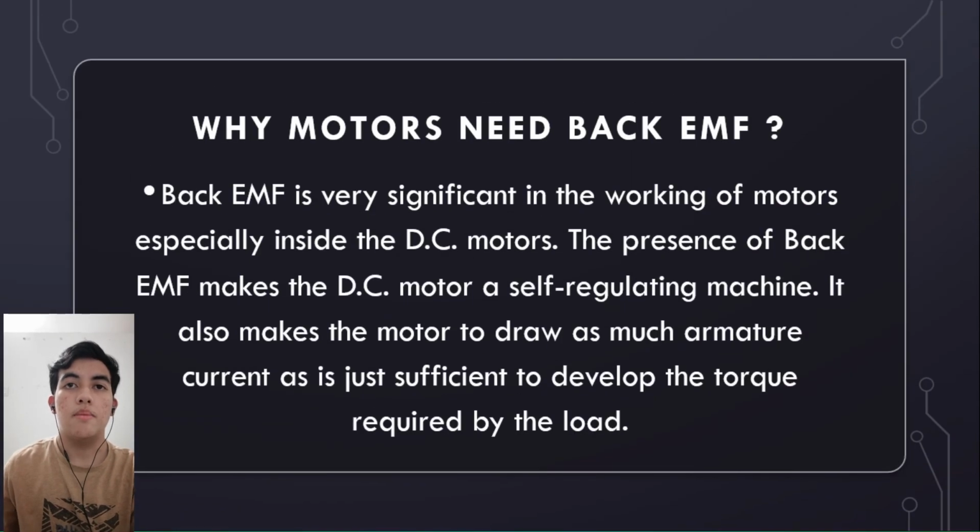Why do motors need back EMF? Back EMF is very significant in the working of motors, especially direct current motors. The presence of back EMF makes the DC motor a self-regulating machine. It also makes the motor draw just as much armature current as is sufficient to develop the torque required by the load. That's all from our group.